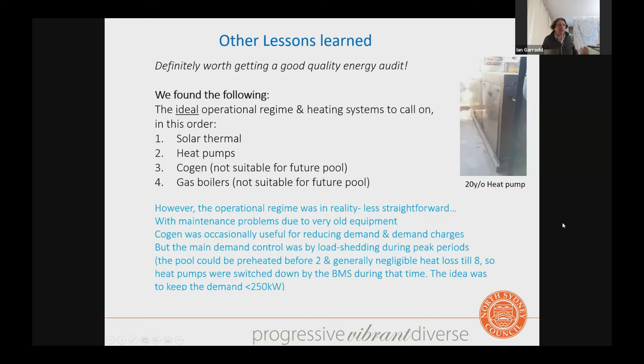That's one thing you can do quite easily with a large body of water - use it as a thermal mass, a large heat mass, and the temperature goes down relatively slowly. So if you want to heat the pool in the morning before electricity becomes expensive, it's a great thing to do. Then you can turn the heat pumps off during the expensive time and turn them back on again to start reheating the pool once the temperature starts to drop a bit. Demand control was something we found very good to implement at low cost because we already had a BMS system in place.